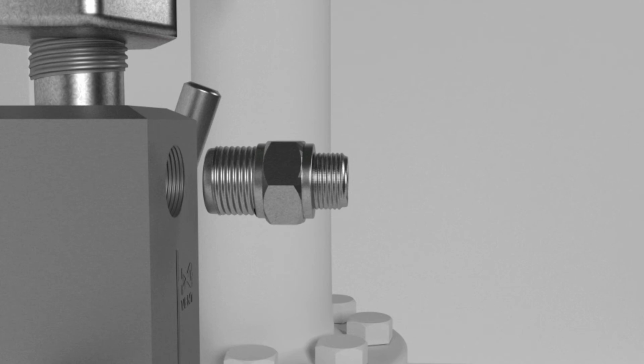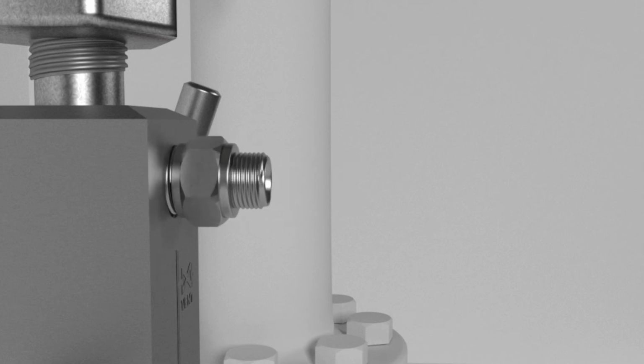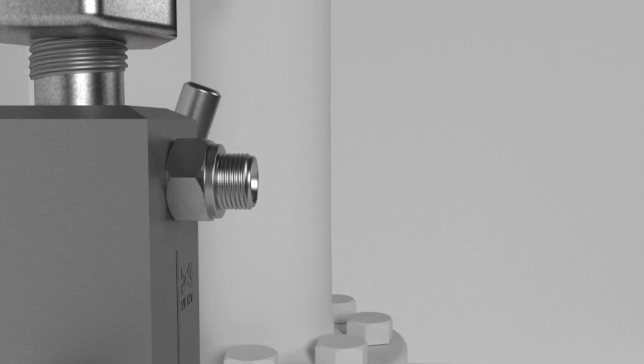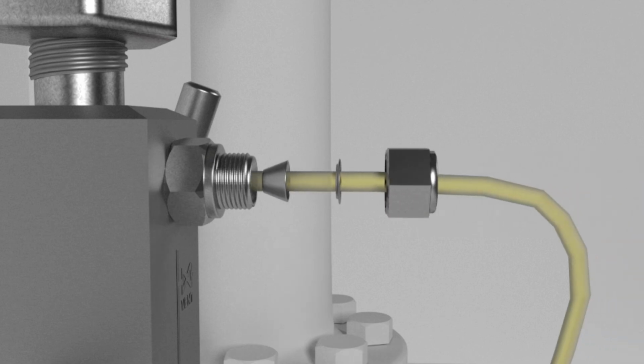Remember to use Teflon tape if the fittings are stainless steel. The connections on the manifold are 1/4 inch NPT female connections. Connect your 1/4 inch NPT to 1/8 inch tube, or 1/4 inch NPT to 1/4 inch tube connection to the manifold.